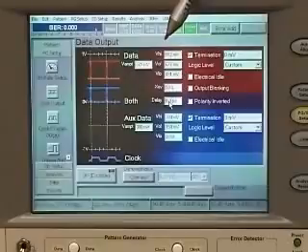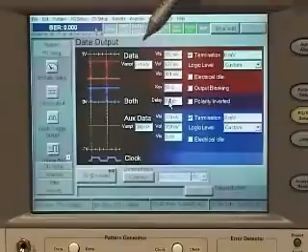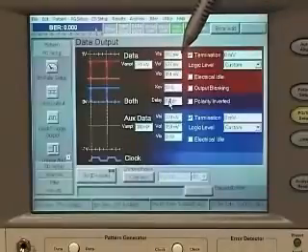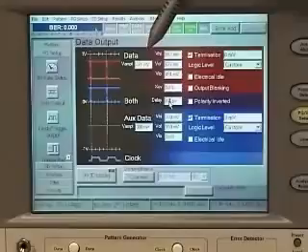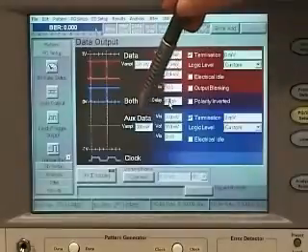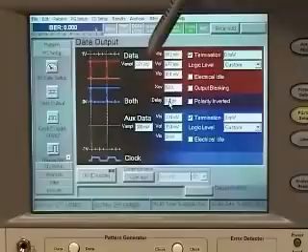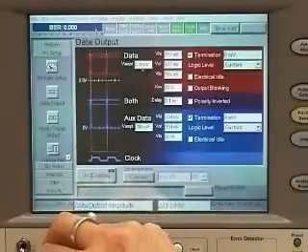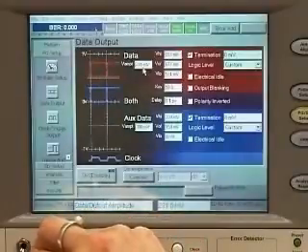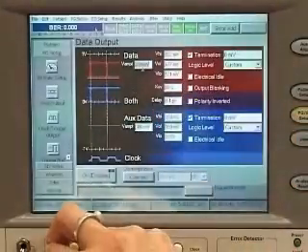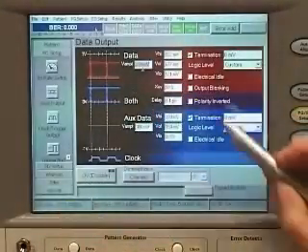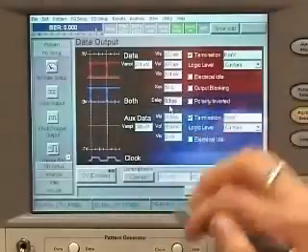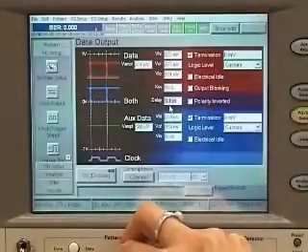This is the new pattern generator output of the J-BERT. Here you can see how to set up the voltage levels and the offset for the data generator output and the auxiliary data output — they can be set up individually. There is also a graphical display showing where in the voltage window your output voltage lies. You can also change the delay between the data and the clock signals.